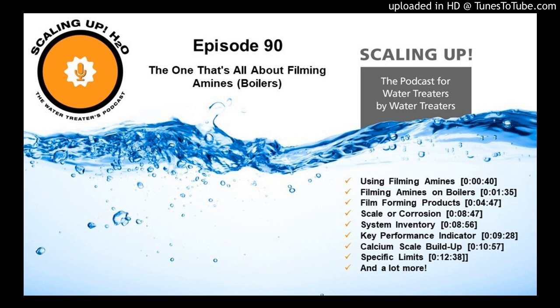When you first bring the chemistry on, when you turn the one set of pumps off and turn on your filming amine product pump, my advice in a known fouled system, or if you're new to filming technology, is cut that in half. Cut that down to 500 parts per million, because it's going to do exactly what we've discussed. It's going to remobilize corrosion material. It's going to start picking at scales. All of that's going to come off.